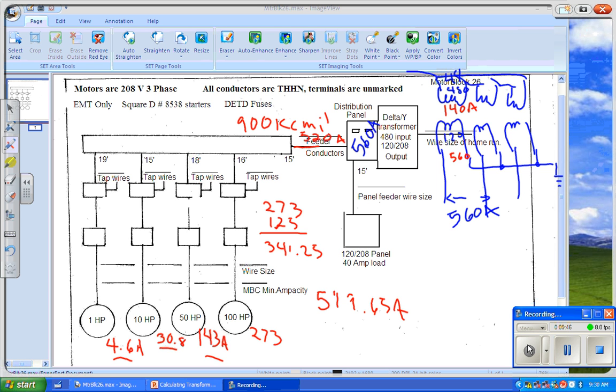And we wanted to do that to find out what supply wires we're going to have to bring to this thing, because from the distribution panel to wherever we're working, where we're bringing this power, we're going to take a home run back to the distribution panel, right? And we need to know what size wires and conduit we're going to have to bring for that. So now we can see that we're going to have to carry 140 amps, right? And so we're probably going to add 25% to that ampacity so that we don't overload the wire. So we know that we want conductors that will carry 175 amps. Can everybody see that? All right.